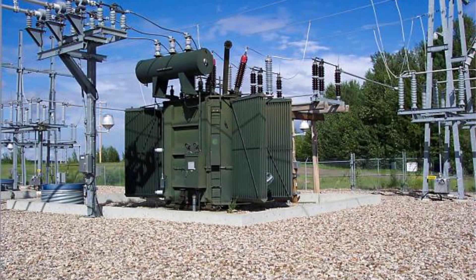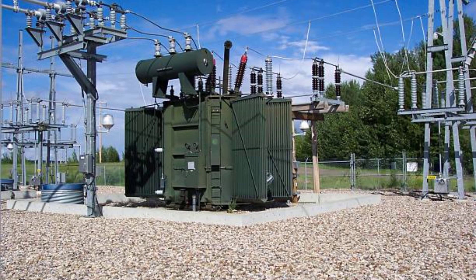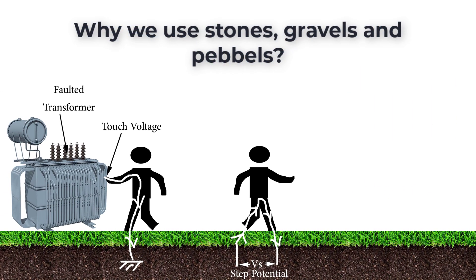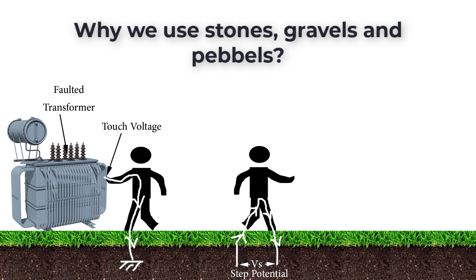For power transformers, we use stones, pebbles, and gravels for more than one reason. The primary reason is to decrease the step voltage and touch voltage by increasing the soil resistance, which will reduce the risk of electrical shock hazards. If you don't know what step and touch voltages are, you can check the touch and step voltages video in the description below to understand it exactly.